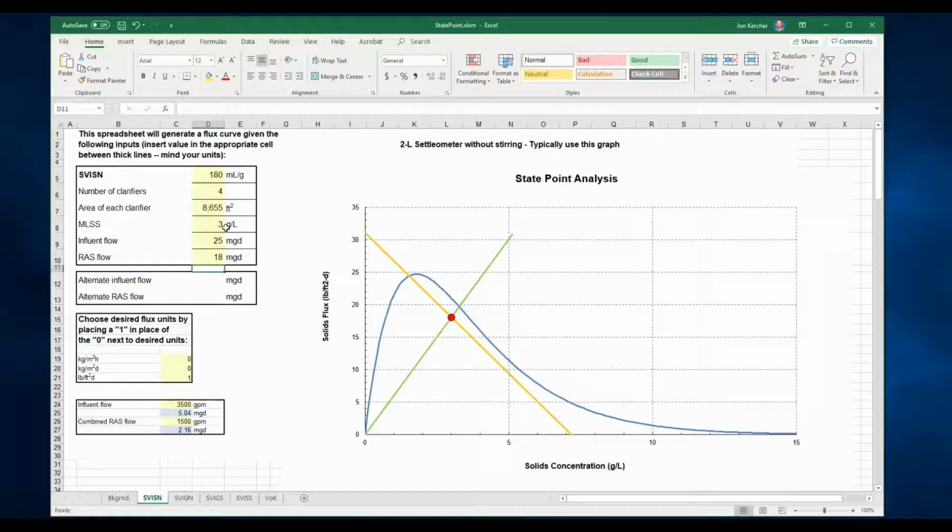When this happens, odds are that mixed liquor is going to fall down anyway. Some of those solids are going to be maintained in the secondary clarifier because of this peak loading rate. And what will happen is my mixed liquor will go down. So if my mixed liquor was to go down to, say, 2,500 in the course of the day, it stands to reason that I've opened up this gap farther. I've also realistically reduced that RAS concentration.